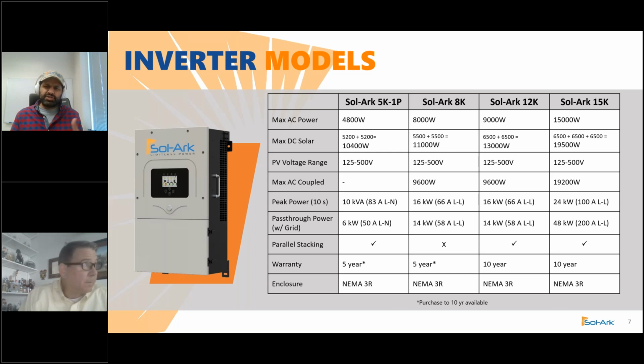The previous versions, the 12K and 8K, were limited in their utility connection in terms of the amount of power they could draw from the utility to about 60 amps. So you could connect, you're only, if you're drawing from the utility, limited to 60 amps. The 15K, you can put your entire 200 amp panel on the load output of the 15K, and when you have grid available, the 15K can draw 200 amps from the grid to the 200 amp panel.